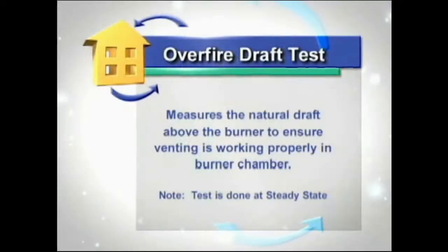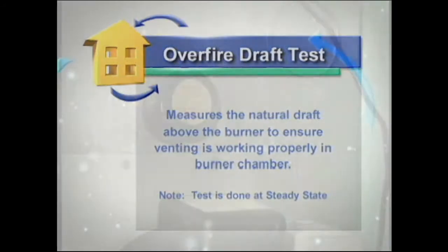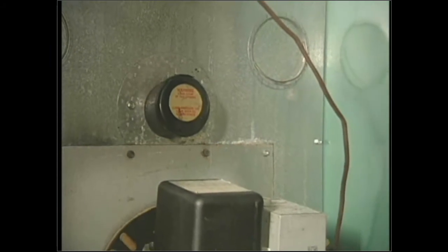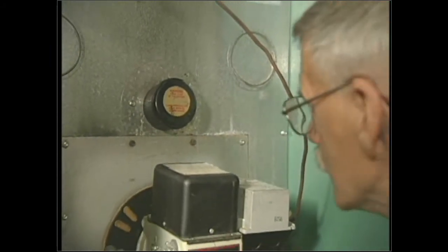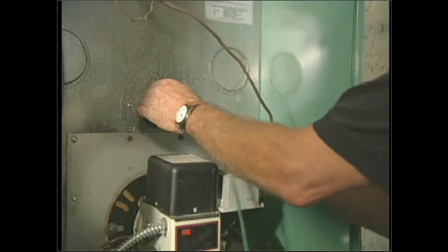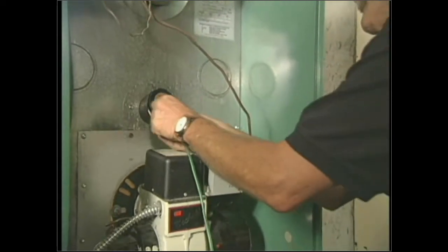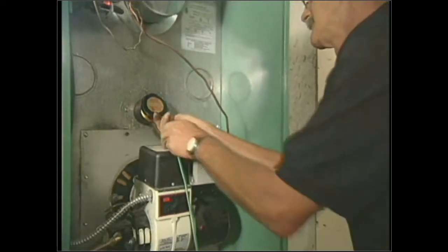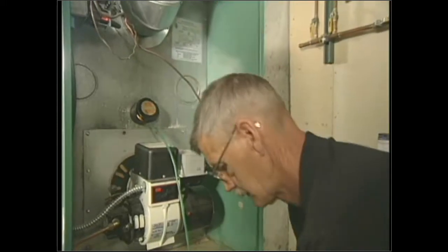Well, the next test that I like to perform is the over-fire draft test. I like to perform it now because the unit is at steady state, I know my draft is adequate, and I have no spillage. Okay? So what I do with that is I go to the observation port, which is located right in front of the furnace, and I open it up, and I'll take a long probe, slide it in, and I close the lid, connect it to my manometer, and then I just watch it, take a reading.